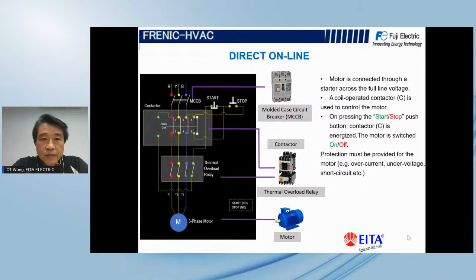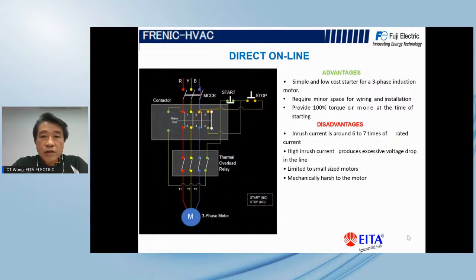It's simple. For direct online, the components you need are an MCCB, basically to protect against short circuit or overcurrent, followed by contactors and also the thermal overload to protect your motor from overcurrent. All these devices can easily be connected up to become a direct online starter. Let's look at the advantages of direct online, especially for the three-phase induction motor. It is basically simple and low cost, you do not require a big space for this direct online circuit, and it provides 100% torque or more at the starting time.